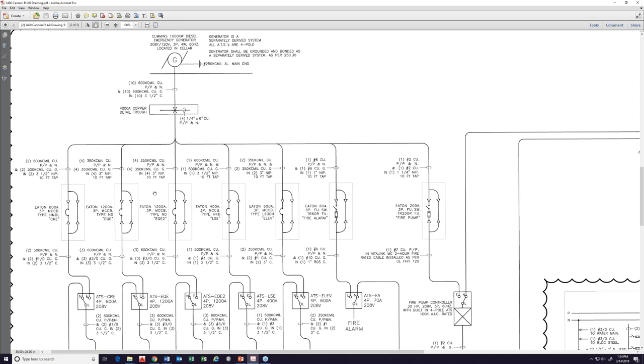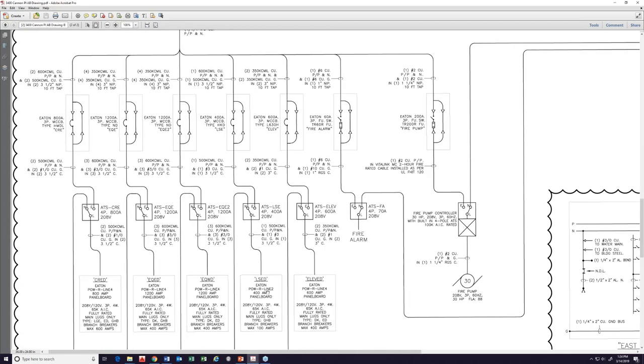And the issue tends to be downstream. For example, if I have a 400 amp disconnect right here, feeding a 400 amp switch, ATS, and then it's feeding an emergency panel board. What some engineers will do is they will have a 200 amp breaker in this panel board. Once you do that, now you're compromising your selective coordination, because it's almost impossible to get selective coordination in circuit breakers 200 to 400 amp.